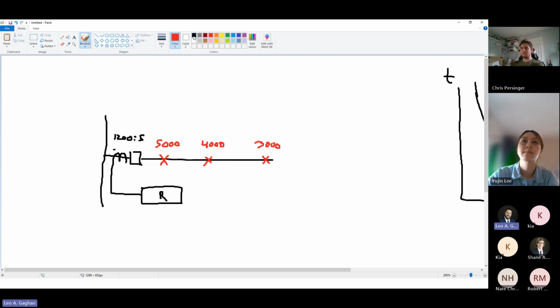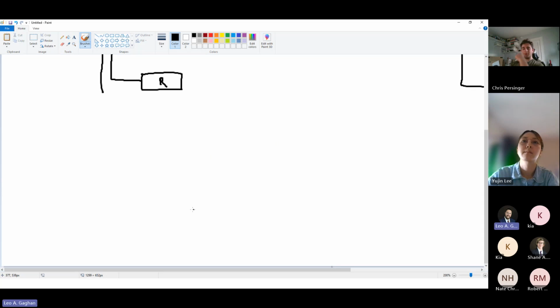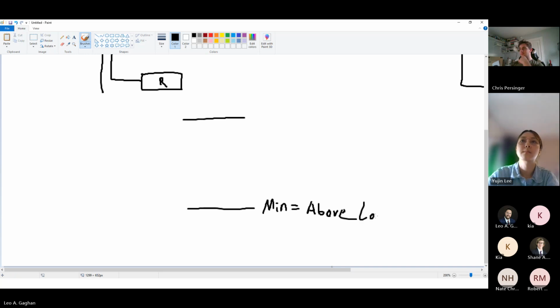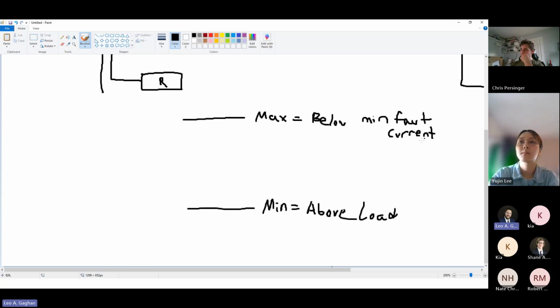So what we end up with is a little bit of a window where we've got a minimum pickup, which needs to be above load. And then we've got a max up here, which needs to be below min fault current. So this is for our pickup.